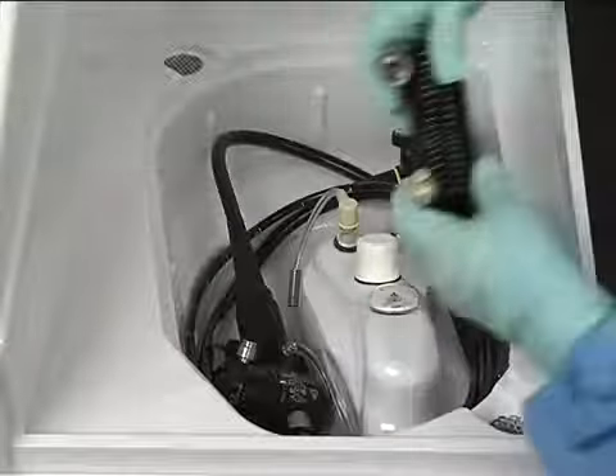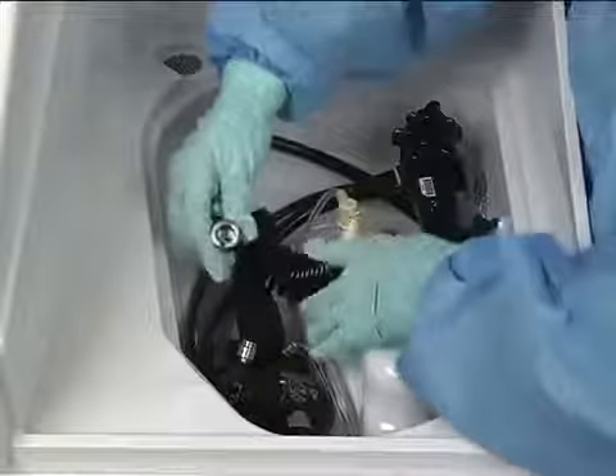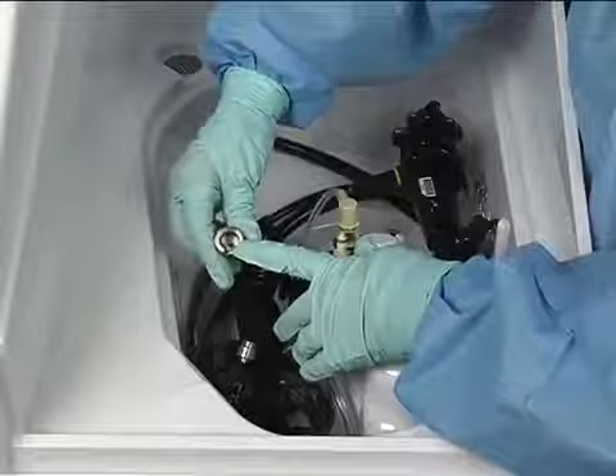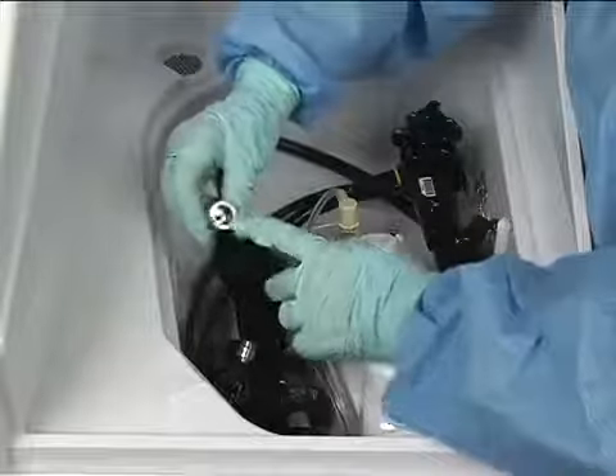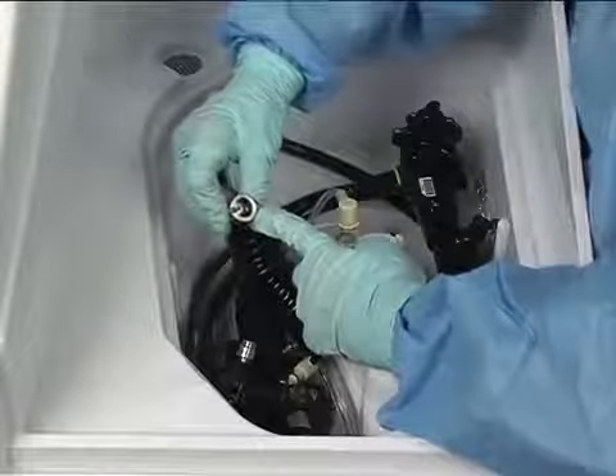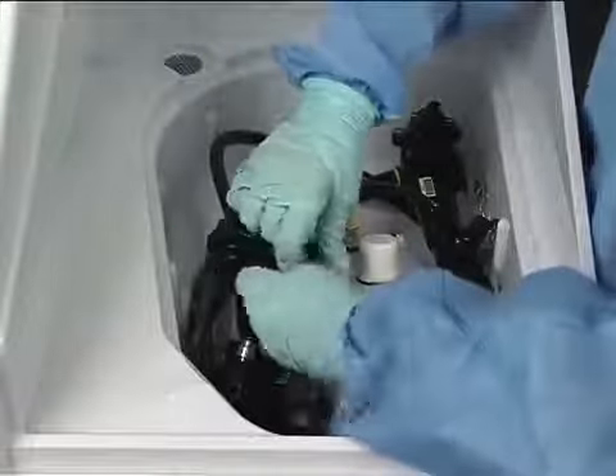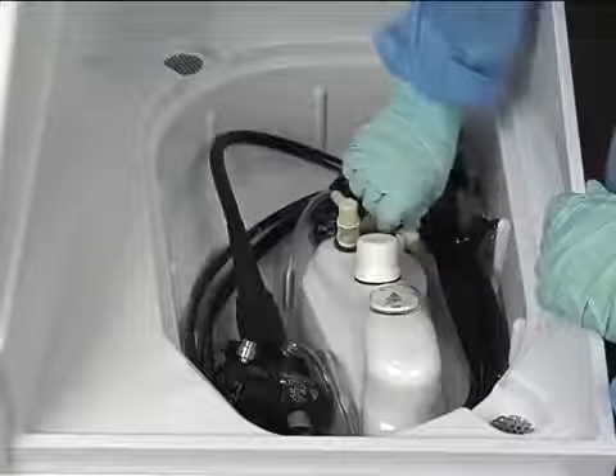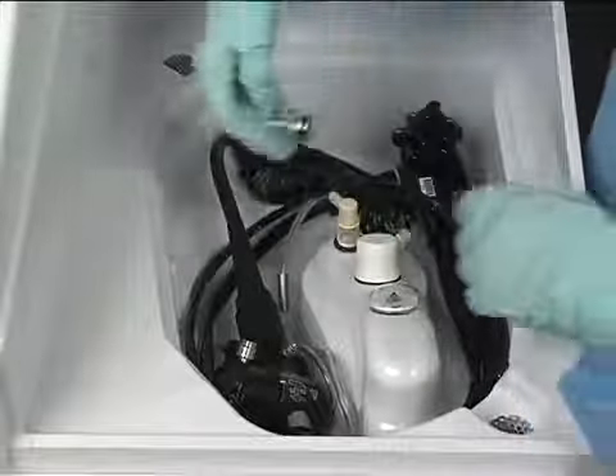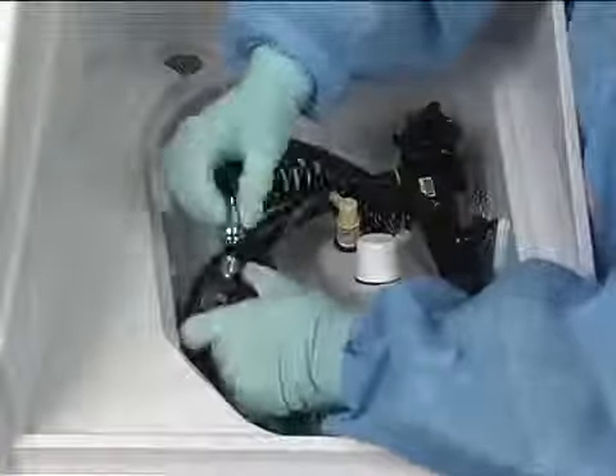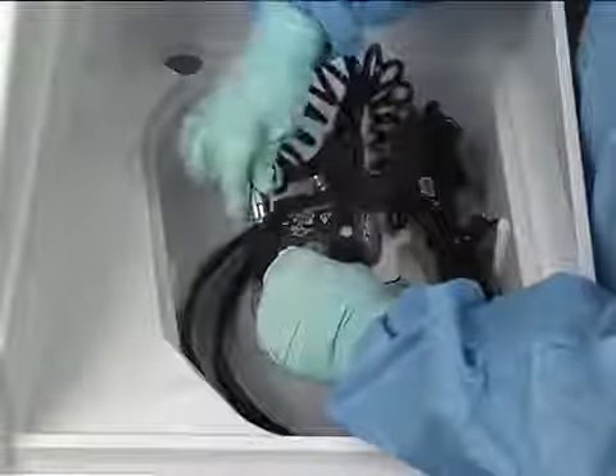The Olympus leak test hookup has an O-ring in the scope connector. Check its integrity and lubricate weekly with silicone oil. All other leak testers should be lubricated weekly with silicone oil to ensure ease of use and a secure connection. Remove the leak test connector from the basin when dumping or reloading the disinfectant. Failure to do this could result in water damage of your leak test system.